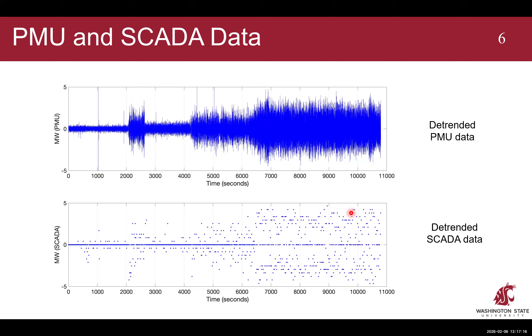Then when the amplitude increases, we are seeing more of those higher amplitude points. And when the amplitude is even larger, the SCADA shows at least some observations with this higher amplitude. That is the signature we see in the SCADA data during oscillations.